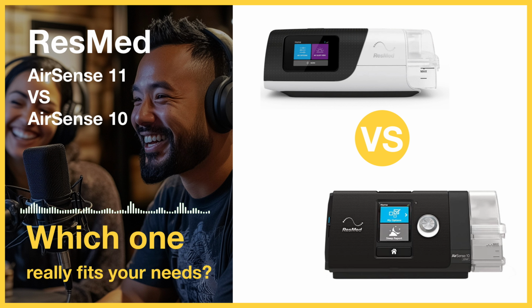The tubing, both standard slimline and heated Climate Line, the humidifier water chambers, and the air filters are all specific to either the AirSense 10 or the AirSense 11. They absolutely cannot be swapped between the two machines. Wow. Okay, so if I upgrade, I need all new everything. Pretty much all the core consumables, yes.